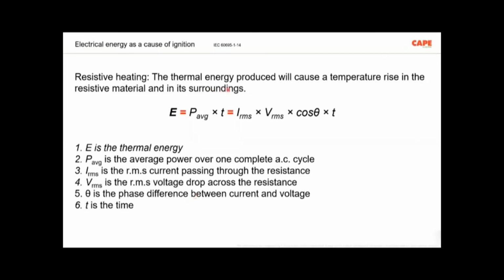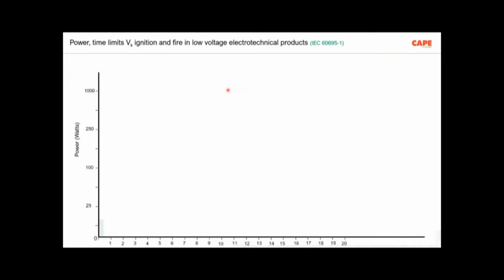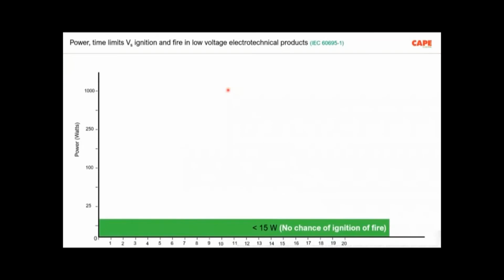I am not going much into depth because these are subjects which require a lot of attention. One simple concept which is followed is that any electrical apparatus which is consuming a power lesser than 15 watts is not supposed to ignite fire. No chance of ignition of fire from an electrical apparatus consuming a power lesser than 15 watts. In the same way, for a device which is consuming lesser than 100 watts, ignition is possible only under certain conditions. What are those conditions? The condition is if some ignitable things are nearby, probably the other items start burning.